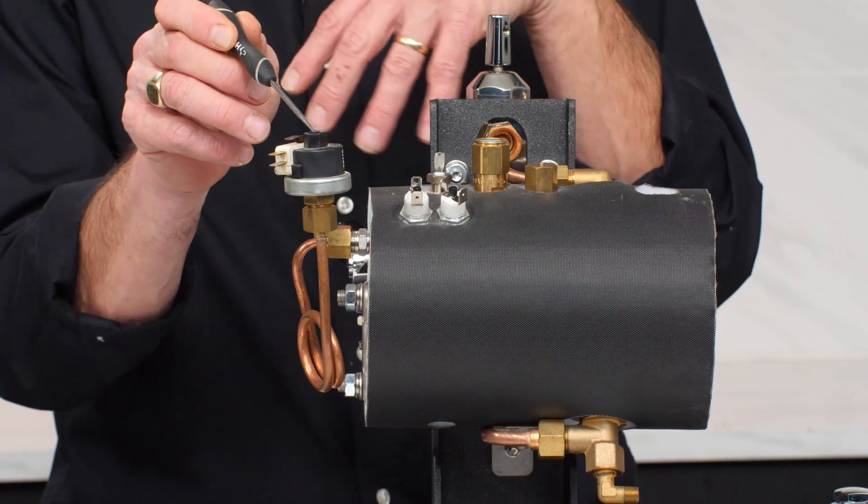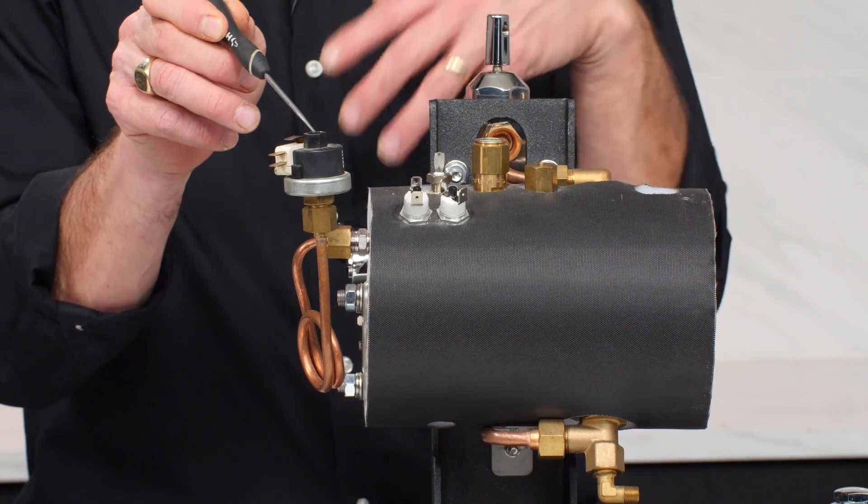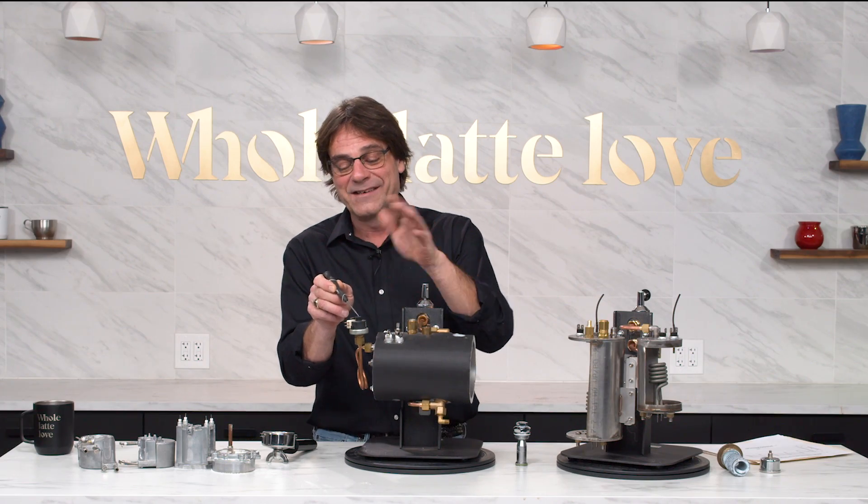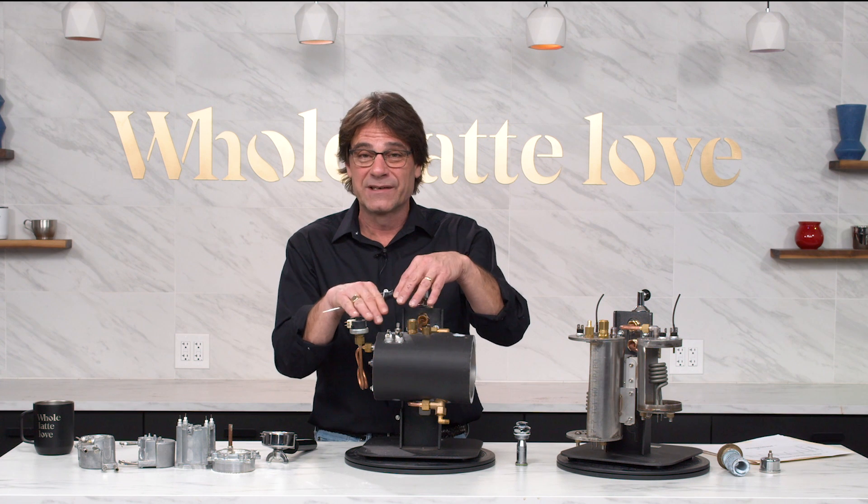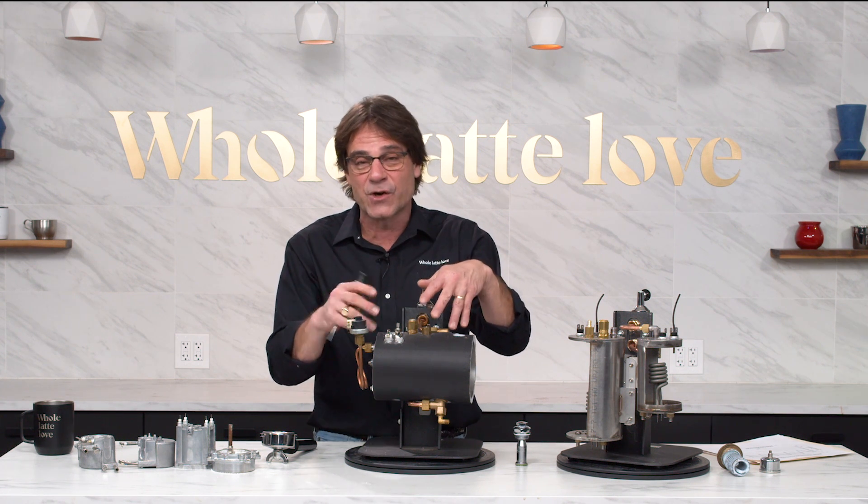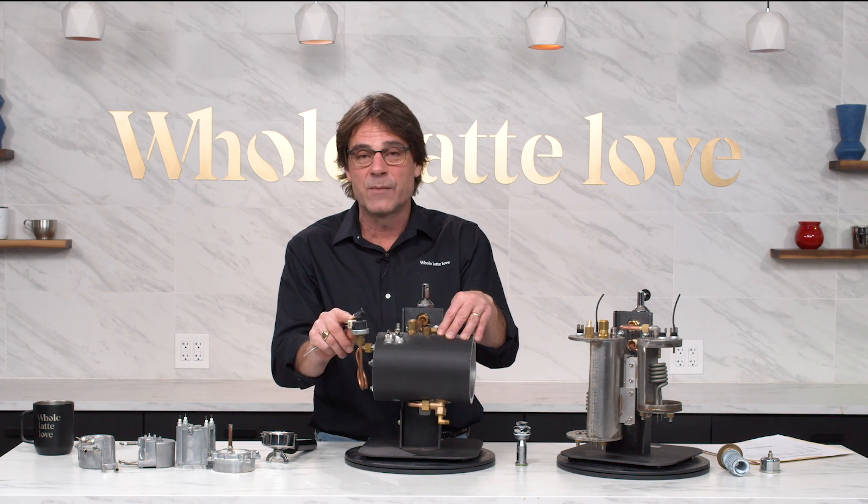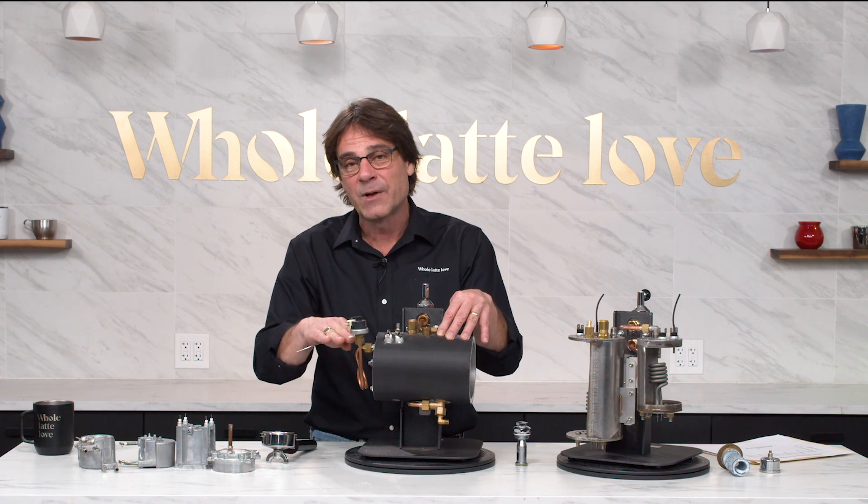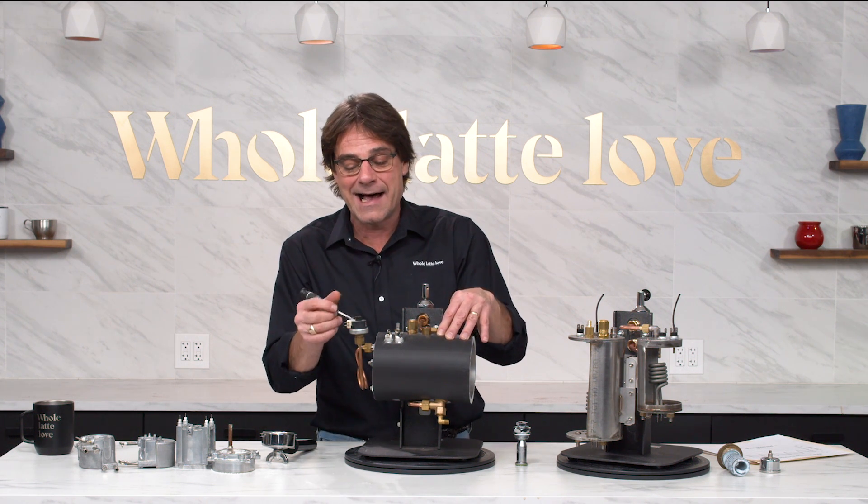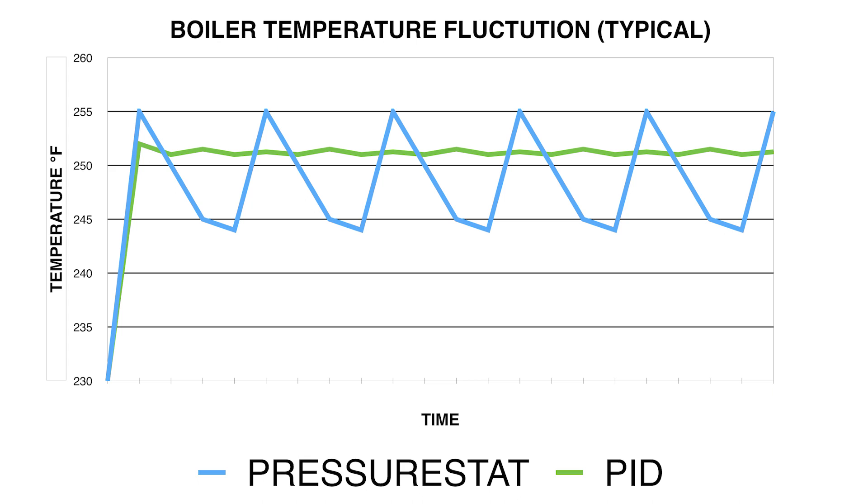This is a pressure stat. In this boiler it's just measuring the pressure that's inside the boiler, and that is going to be connected to the heating element and tell the boiler when to heat and when to not heat. So the boiler reaches a certain pressure which relates to a temperature. When it reaches that pressure, it kicks the element off, then the pressure is going to drop, then the element's going to kick back on.